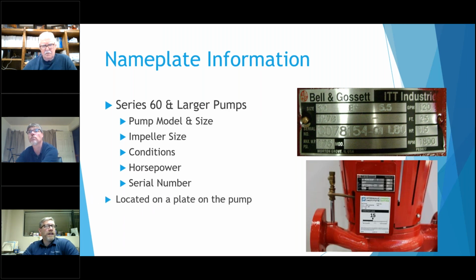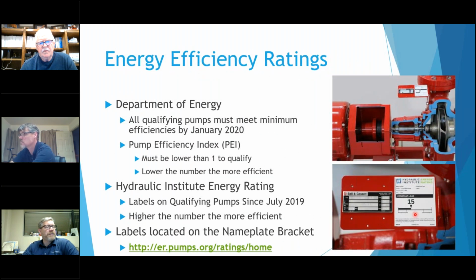Smaller pumps put a sticker on the bearing assembly, which has probably been changed out since you got it. You can see these stickers. These are the PEI and the ER ratings of the pumps from the Hydraulic Institute. B&G puts them on all of them. Again, the pump efficiency index has to be less than 1 in order for the pump to be sold. It's almost like an Energy Star type sticker, where you can compare the pumps to one another.